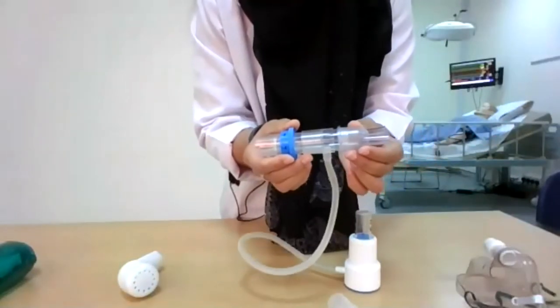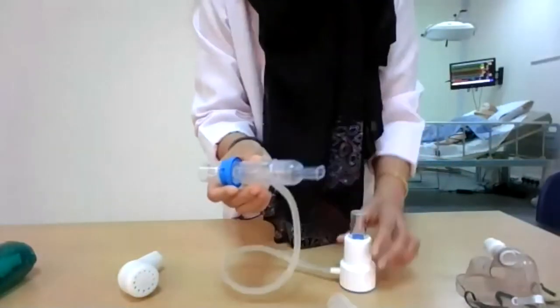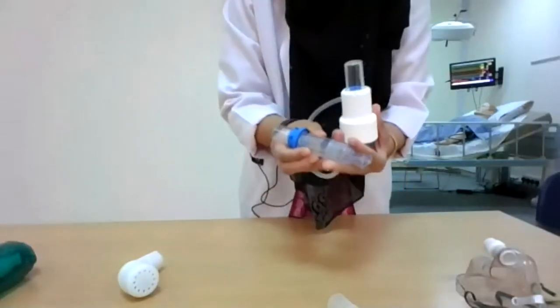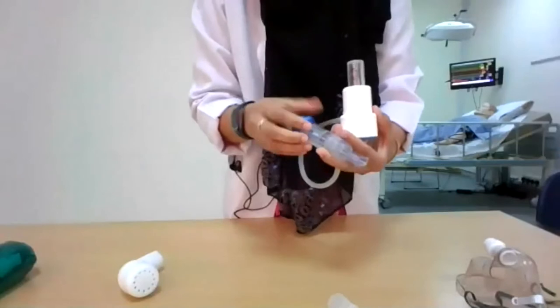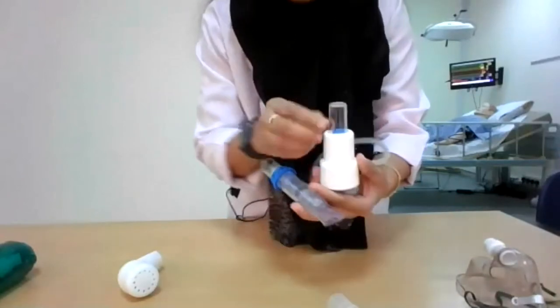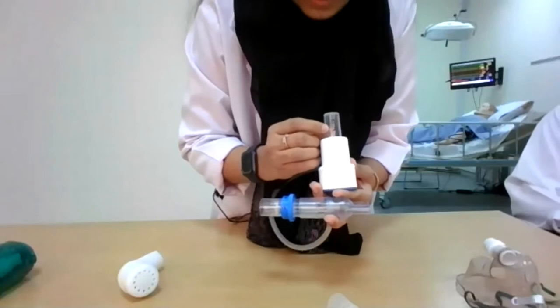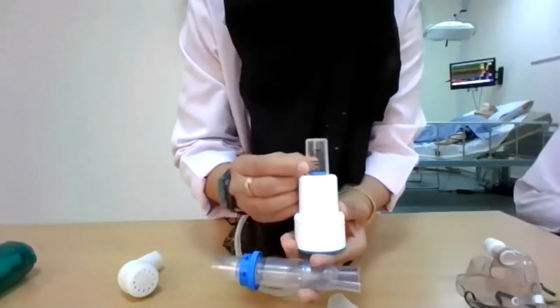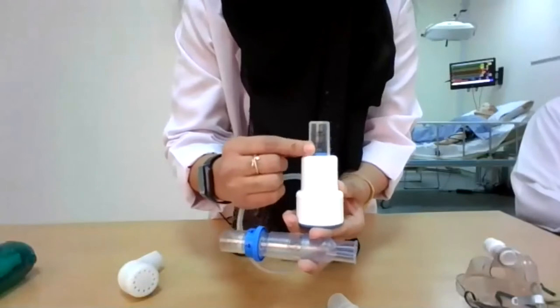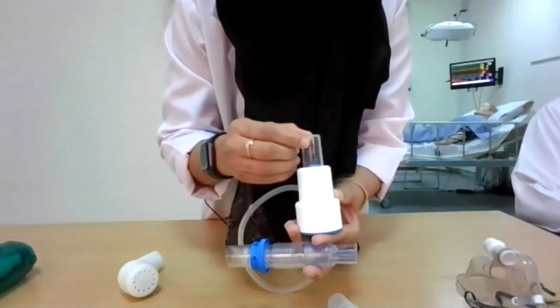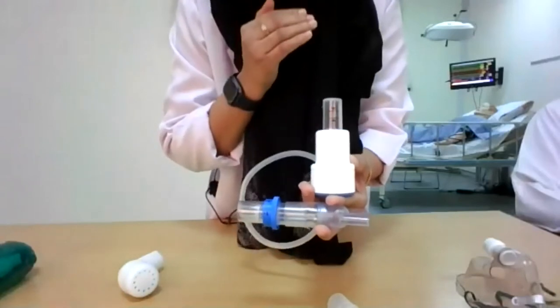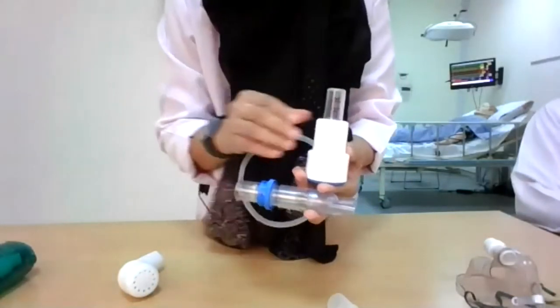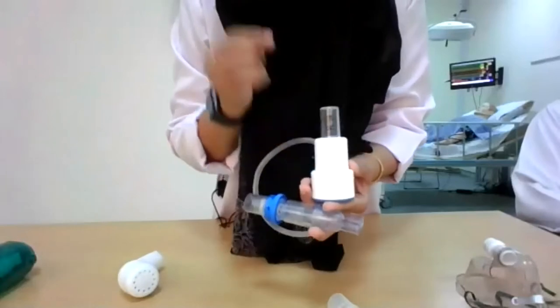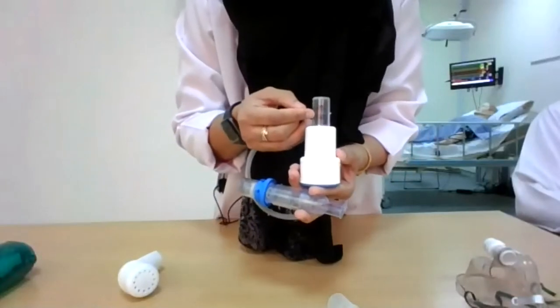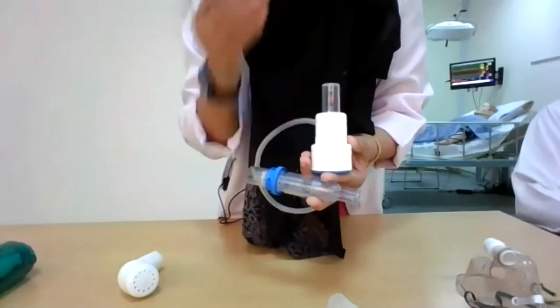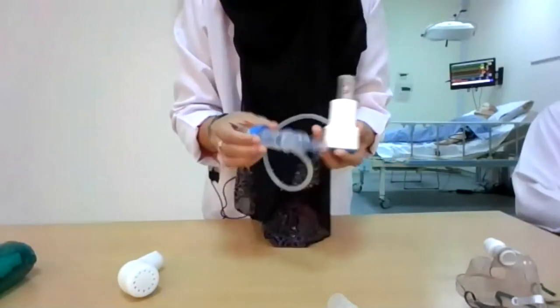So this mouthpiece can be connected here, and one of the most important features of this device is that during exhalation, the patient can monitor his pressures between these two indicators. There are two indicators here. The lower indicator indicates a pressure of 10 centimeters of water, whereas the other one is 20 centimeters of water. During the entire exhalation, the patient should maintain a sustained pressure between these two. It should not go beyond 20 and it should not be less than 10 centimeters of water.